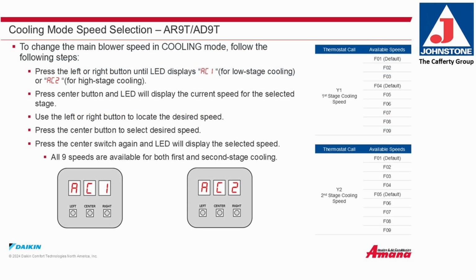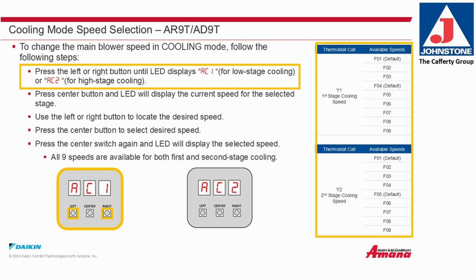Cooling mode speed selection. To change the main blower speed in cooling mode, follow these steps. Press the left or right button until the LED displays AC1 for low stage cooling or AC2 for high stage cooling.